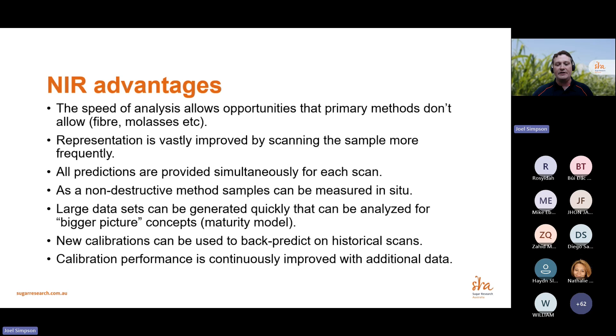So with new calibrations, there's also a thing called spectral legacy is the word I was after, sorry. You can go back in history and look at scans that you've previously collected. If you've got a new calibration for something new, a new measurement where you want to see what happened in history, you can take that measurement and back predict on all those spectra that you have, and get predictions for scans that are long past in history. So it's quite useful in that regard as well. And the other thing that we tend to do is always try to improve calibration performance by building in new data as it comes along. So if there's some other factor that we need to consider, we can include that and get a better model and better predictions.